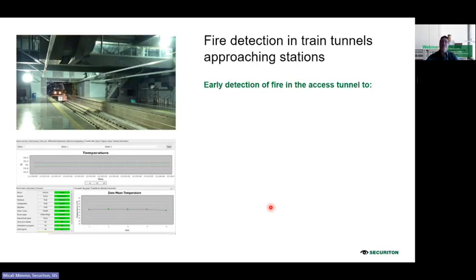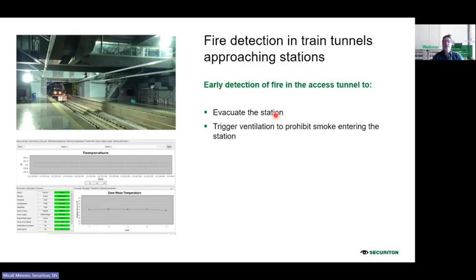Then fire detection, which is also very interesting, is that once we can detect a fire in a tunnel, maybe close to a station, if you are talking about a metro tunnel, we also need to evacuate the people that are waiting here on the platform. So therefore it's important that we also detect the fire inside the tunnel, because the smoke will come out of the tunnel and will be dangerous for all the people waiting on the platform. So therefore we also need to trigger the ventilation to de-smoke.